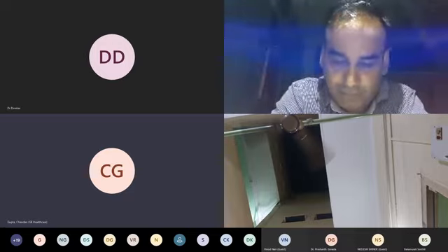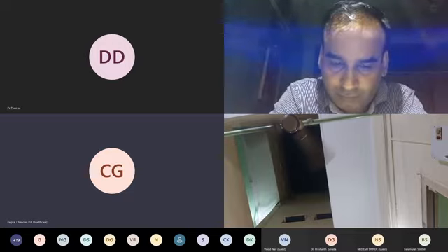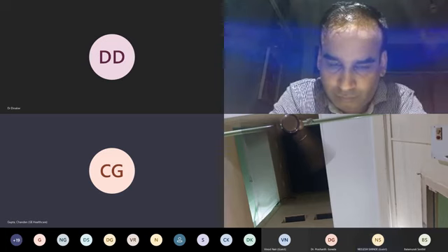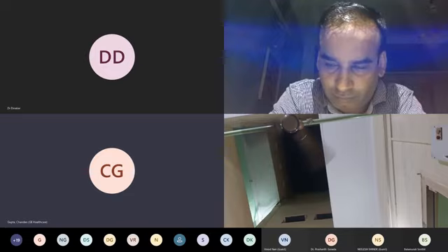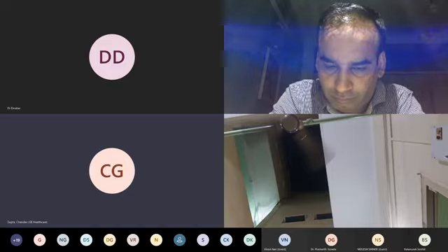So if there will be a noise of the fan which the babies will be hearing, how can you design a fan with very low noise so that the overall noise factor is less? These are the different things that we have done for each one of these cases that I talked about, to reduce the stress level of the baby, so that we can create an environment almost like a mother's home. I talked about a cascade control mechanism versus the PID control mechanism that's being used in most of the incubators.